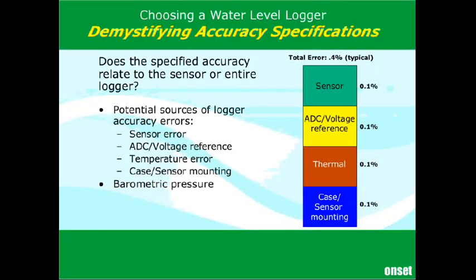It's also important to consider the whole measurement error, which not only includes the pressure logger, but also potentially a barometric logger, or in the case of a vent system, the vent system error, and the manual measurement error that everything is referenced to. Regarding the pressure logger error, one has to consider the case sensor mounting error. A pressure sensor is a strain gauge measuring the strain of the sensor diaphragm acting over pressure. Mounting of the sensor must not induce additional strain to the diaphragm, especially over temperature and pressure ranges, while also preventing a leak path around the sensor.